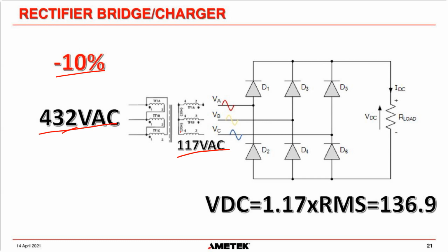And then if we did the calculation, that means the output voltage now goes down to 136.9. So if there is a fluctuation on the input and we only use diodes on our bridge, there's going to be a fluctuation on the output DC, which isn't good. If you had batteries connected here, that would possibly undercharge your batteries because the voltage has gone down.